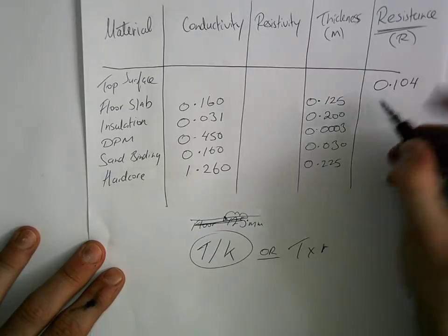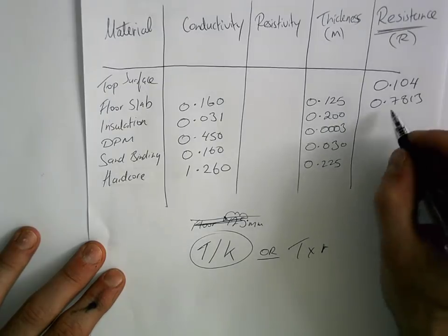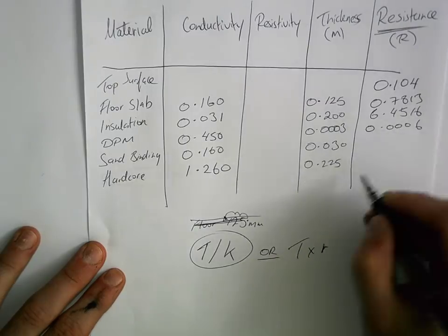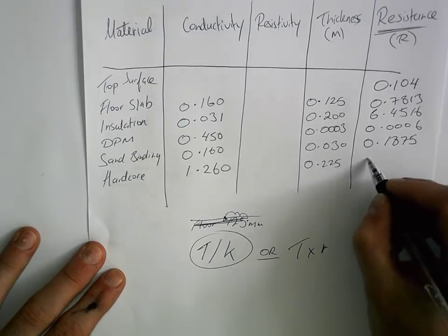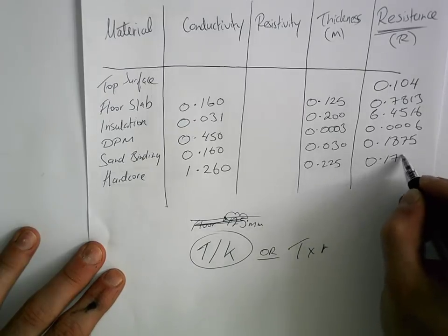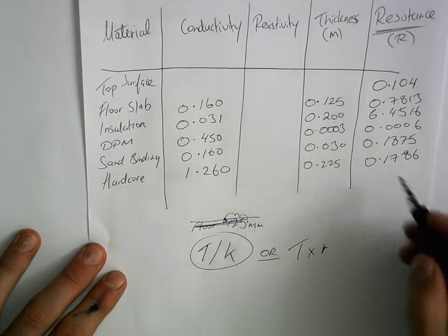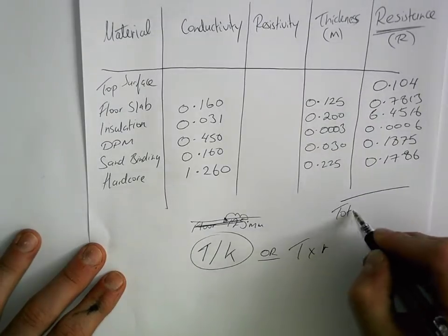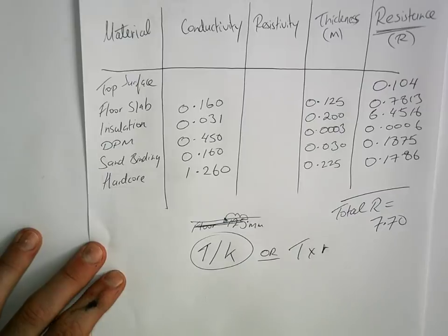The resistance values are: floor slab 0.7813, insulation quite high at 6.4516, DPM almost non-existent, sand binding 0.1875, and hardcore 0.1786. Three decimal places is enough for full marks. The next stage is to total all your resistances — just add them together — giving a total resistance of 7.70.